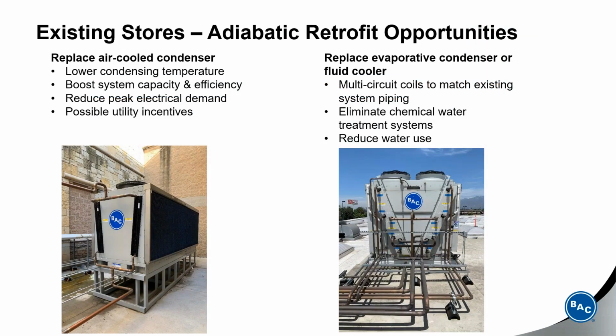Adiabatic can also present many opportunities for retrofit in existing supermarket systems. Replacing an air-cooled condenser and not changing anything else in your system, you can immediately realize lower condensing temperatures, which can mean either a boost in your compressor capacity or just much more efficient operation. It could also reduce peak electrical demand, which could lead to the possibility for some utility incentive rebates with your local utilities. I'll highlight an example of this in one of the case studies to follow.